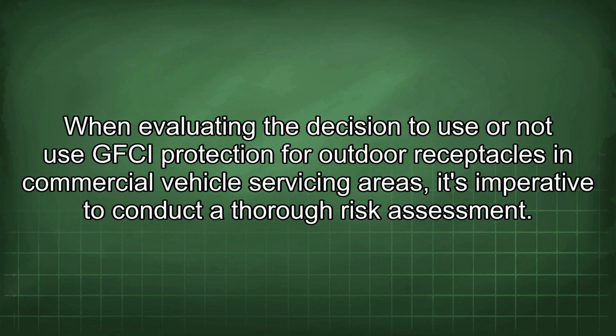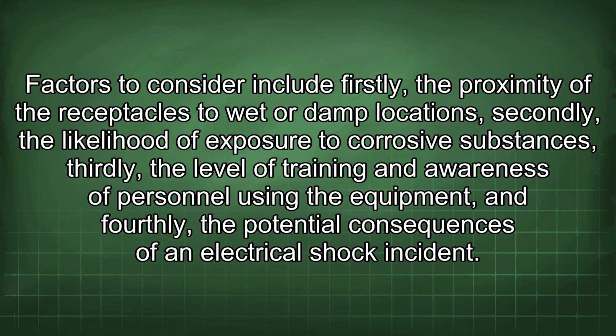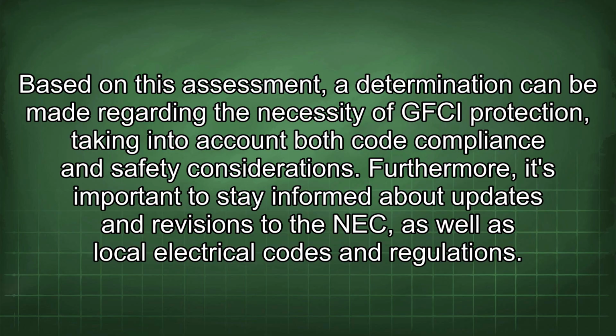When evaluating the decision to use or not use GFCI protection for outdoor receptacles in commercial vehicle servicing areas, it's imperative to conduct a thorough risk assessment. Factors to consider include firstly, the proximity of the receptacles to wet or damp locations, secondly, the likelihood of exposure to corrosive substances, thirdly, the level of training and awareness of personnel using the equipment, and fourthly, the potential consequences of an electrical shock incident.